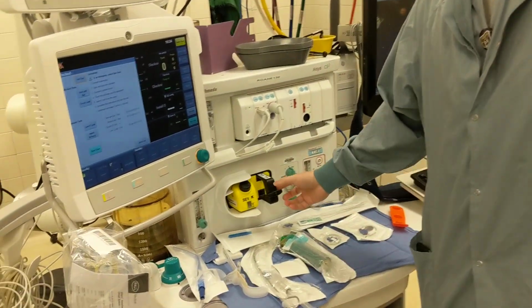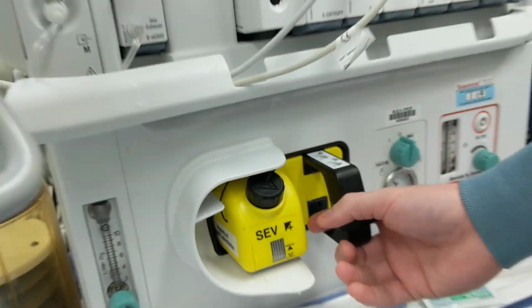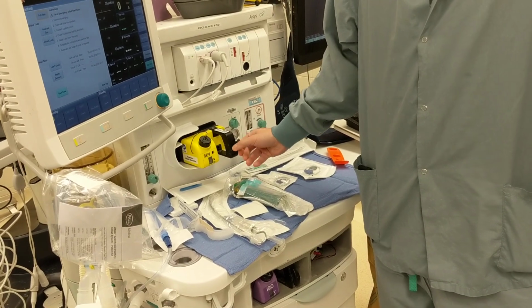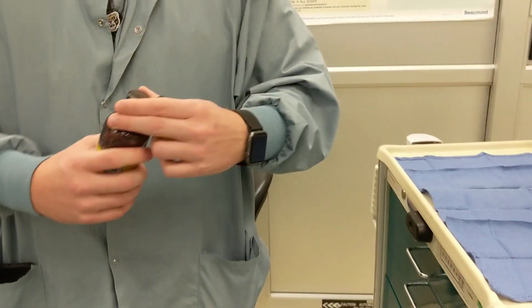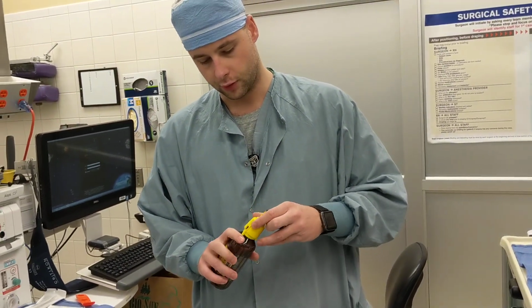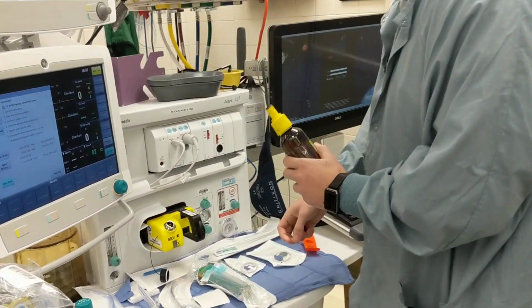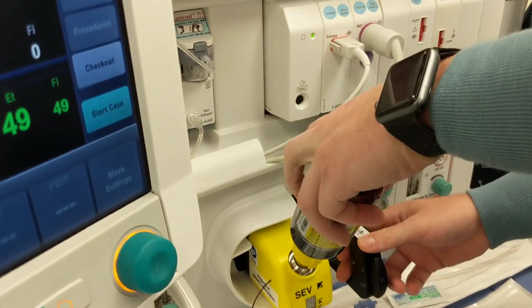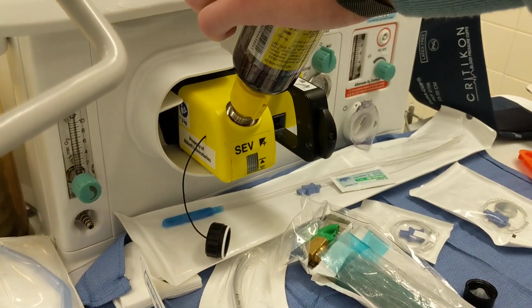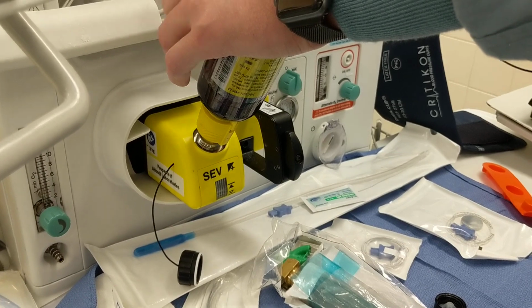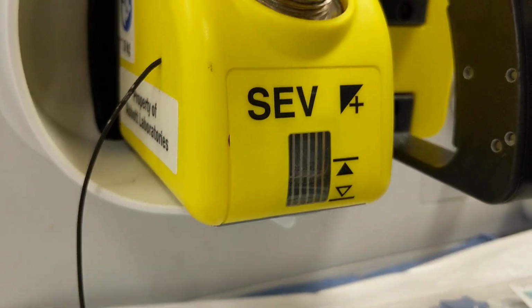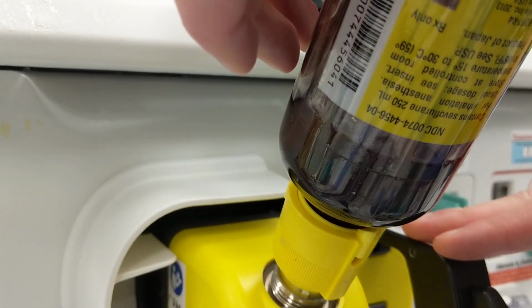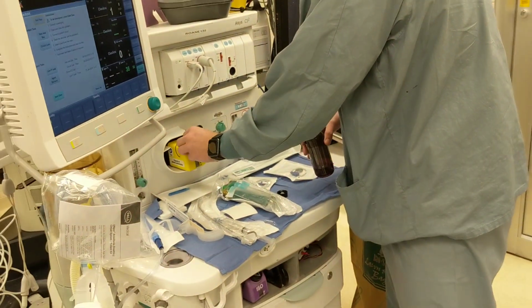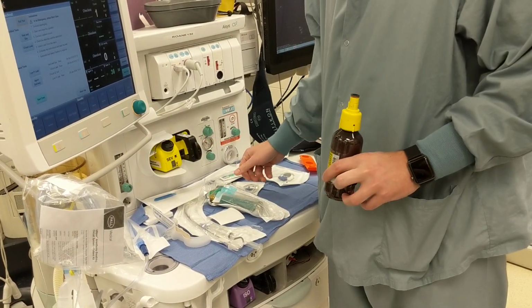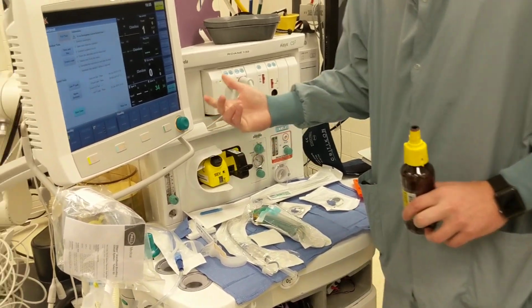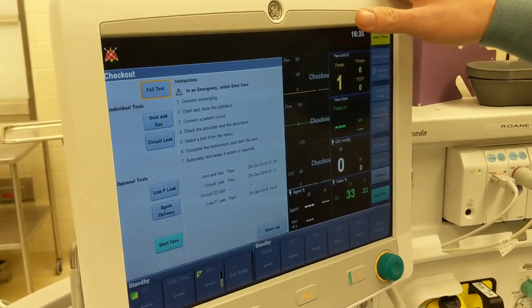You can see our vaporizer here is a little low, so we're going to go ahead and refill that. Unlock it by turning this knob here. Take it off. Each individual vaporizer will have a specific lid for it. Throw on the lid. Tightly so you don't have any leaking while it's going. Line up. And simply just press down. And we can see the level of the vaporizer rising. To relock, cap back on, back into place, so you hear a click, and then turn the lock, so we're not going anywhere. While you've done that, your machine is now on, and we can start with our full checkoff.